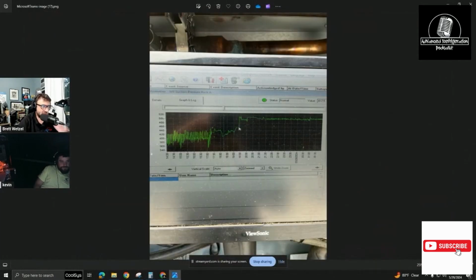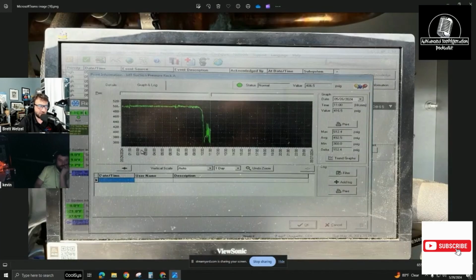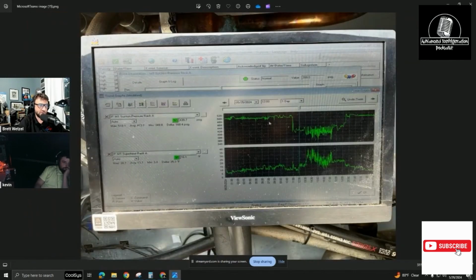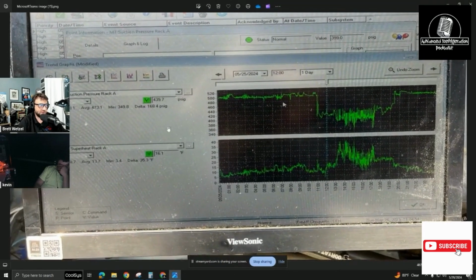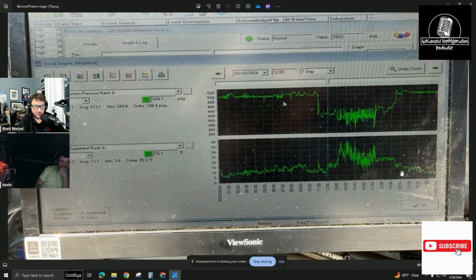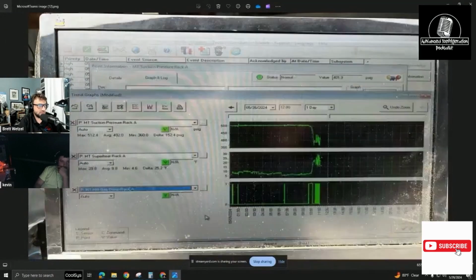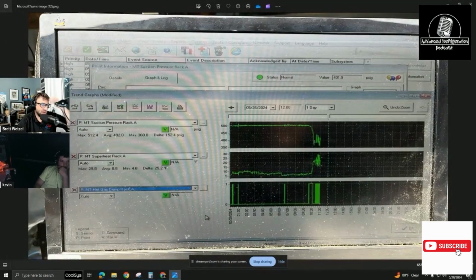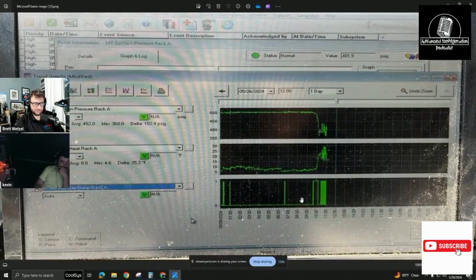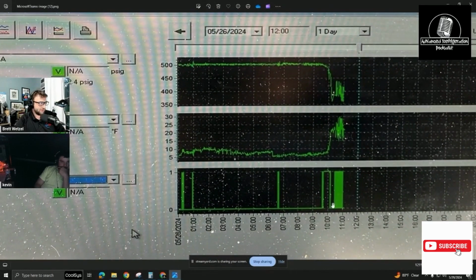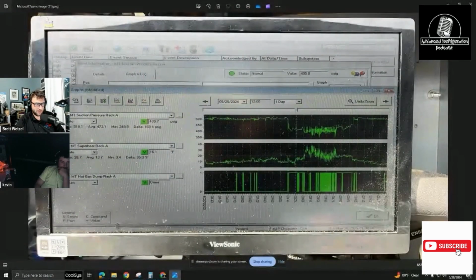Anyway, all right, filter. And you can see the suction pressure basically fail, and it failed right around this 6 o'clock mark. So we were trying to figure out why it failed. Fine, turns it back on, and then right around 6 o'clock fails again. So that's when we started looking at, okay, suction pressure, superheat, fine, then drops. And so, okay, good, it's still switching. Okay, so then we started graphing the hot gas dump. Seems like it's doing something. I know it wasn't feeding as much as what it should have been.